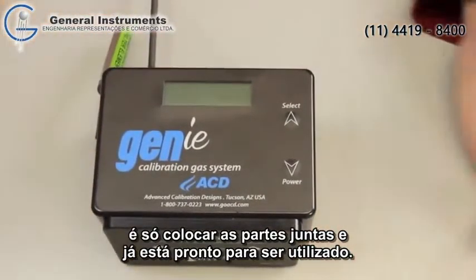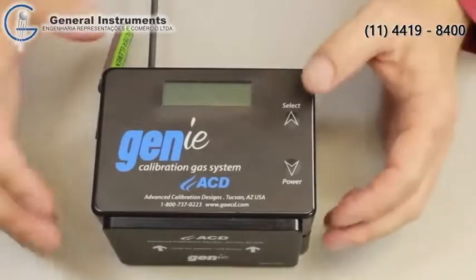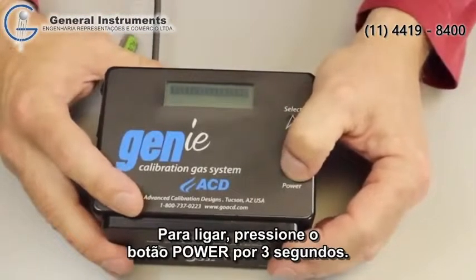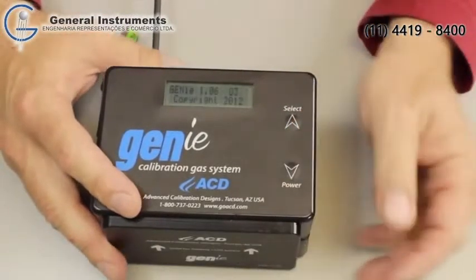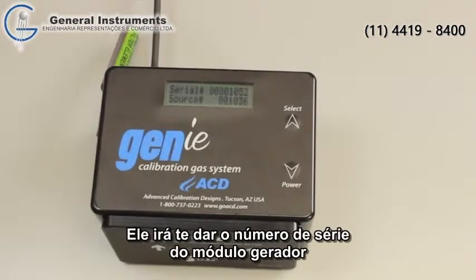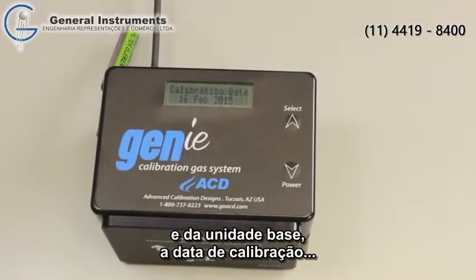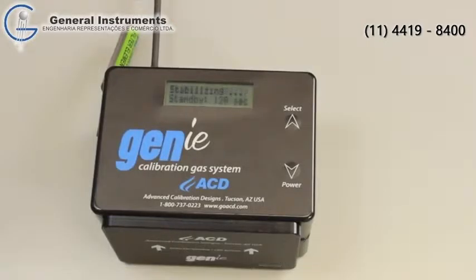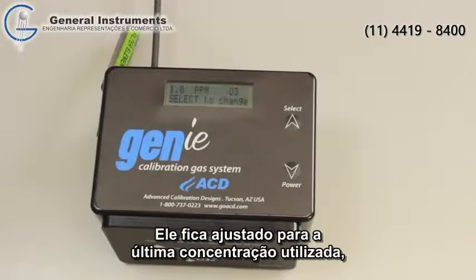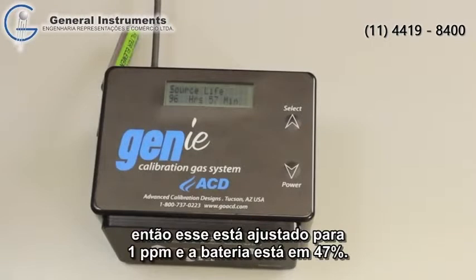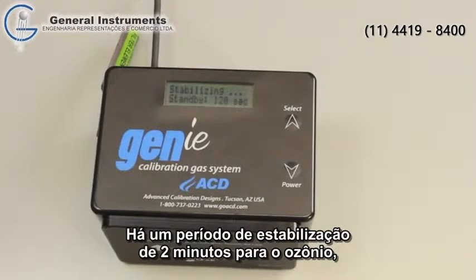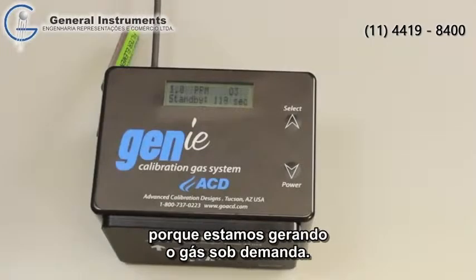Let's say I've got this thing put together and ready to go. To turn it on, you press and hold the power button for 3 seconds. All right. It gives you the serial numbers of the source and the base unit, gives you the calibration date, and it comes up to whatever concentration you ran it at last. So this is giving me 1 part per million. It says the battery's down to 47% of life. And there's a 2-minute stabilization period for ozone because we are generating the gas on demand.